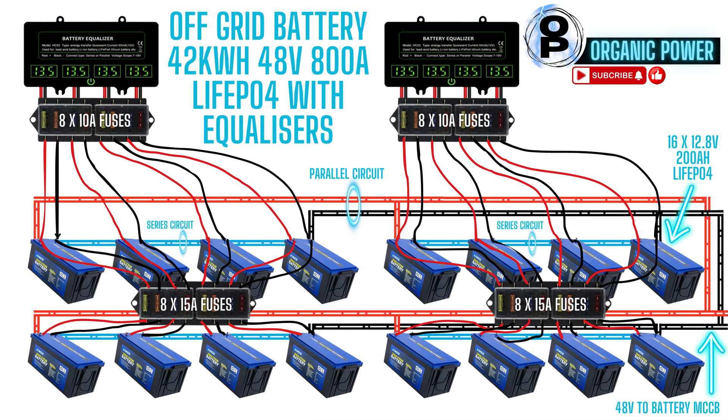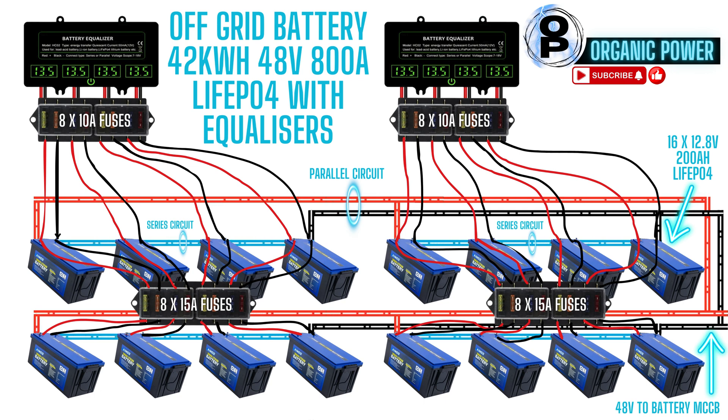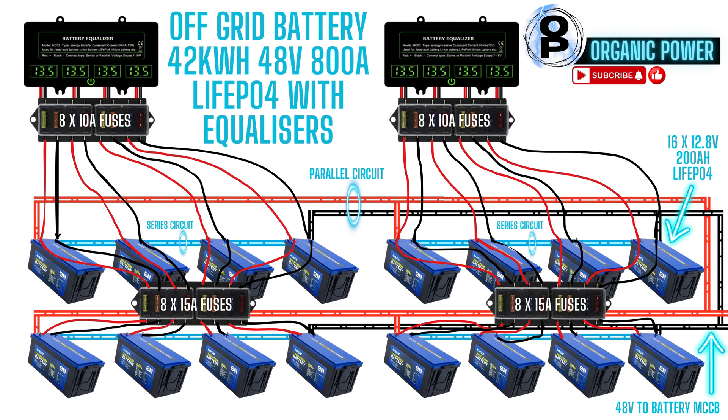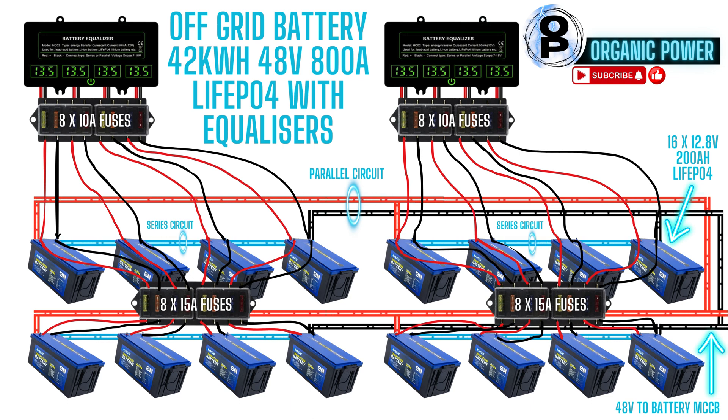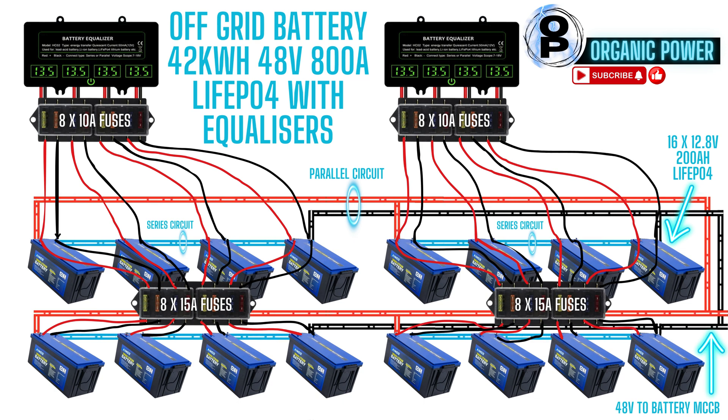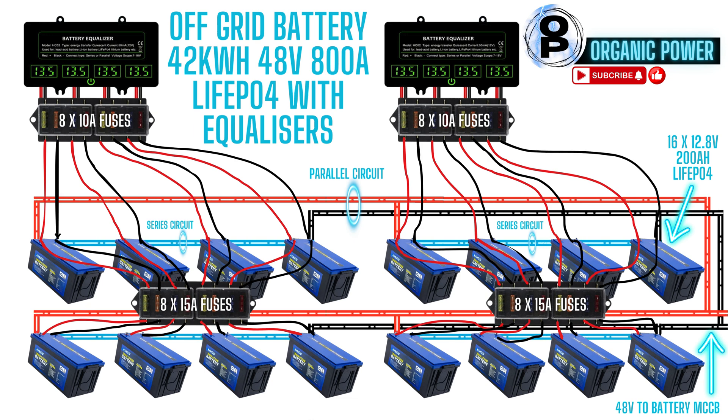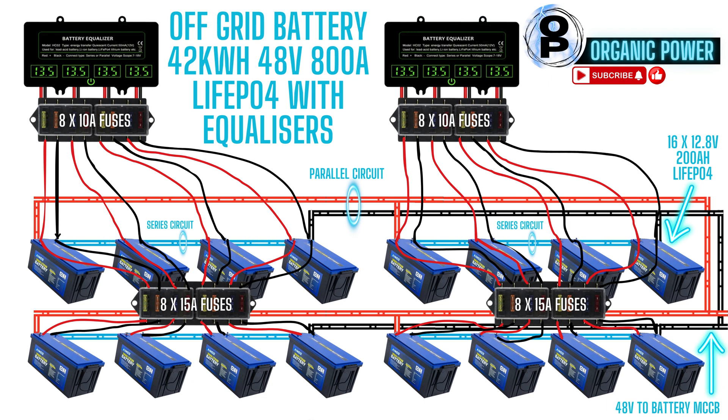In a series circuit, voltage is added. So we have the four 12.8 volt batteries, that voltage is added together. This will give us our 48 volt bus. The bus actually runs at around 53 volts when we're at 100% and the system is beginning to discharge in the afternoon.